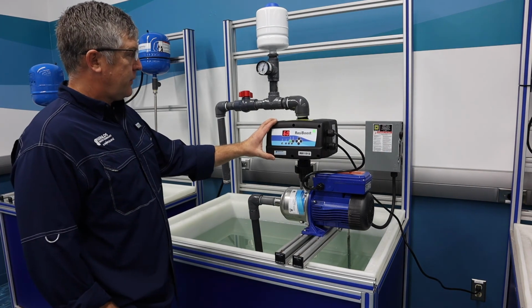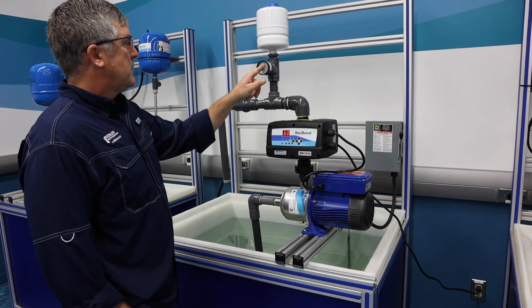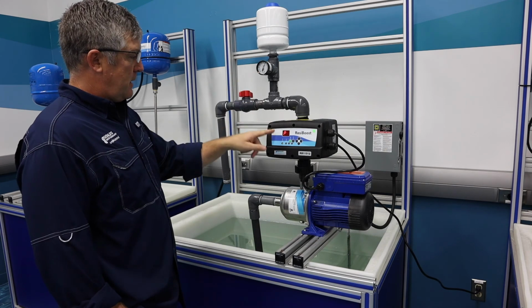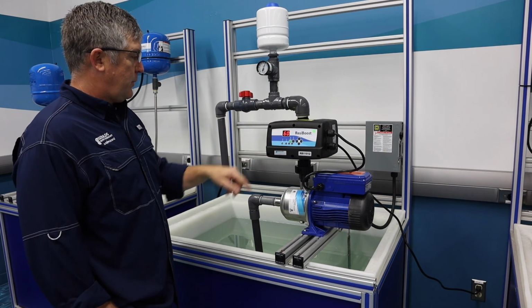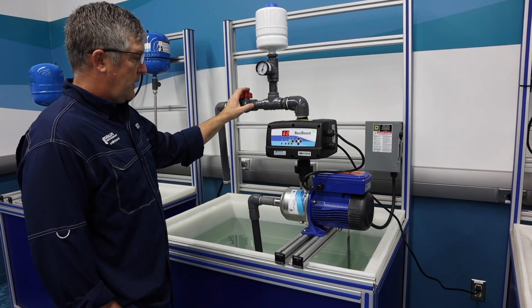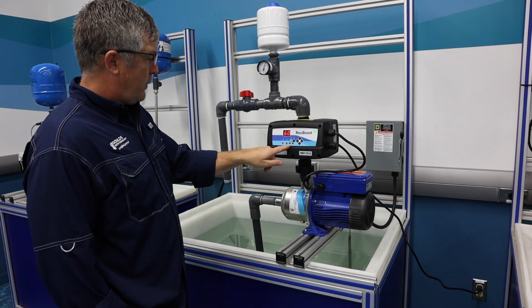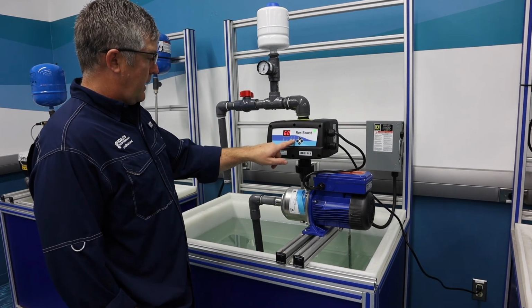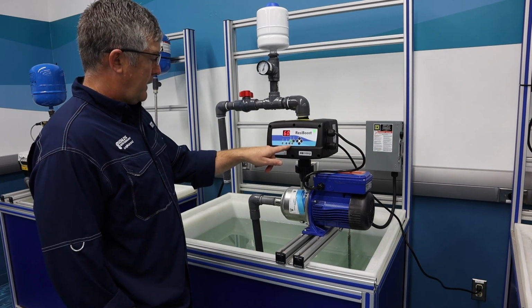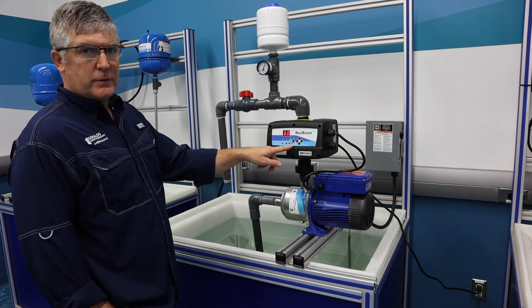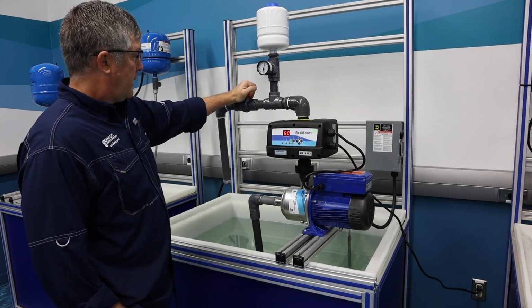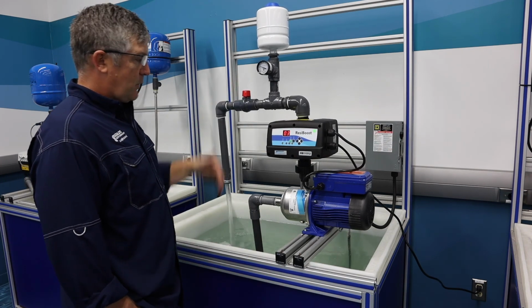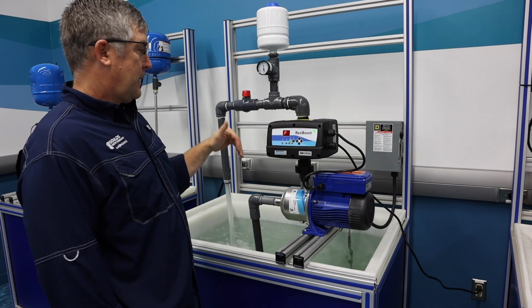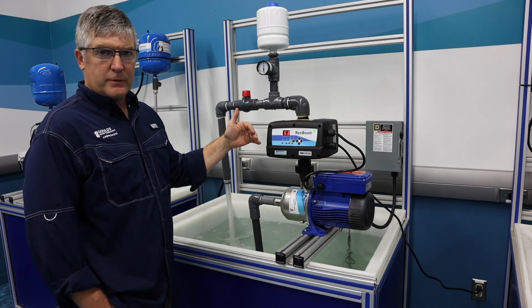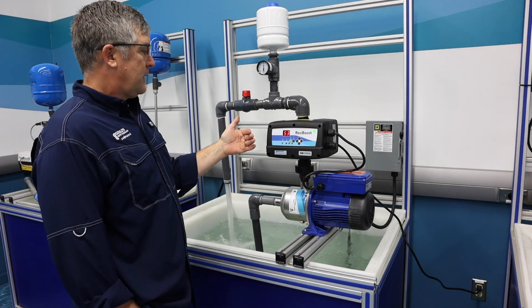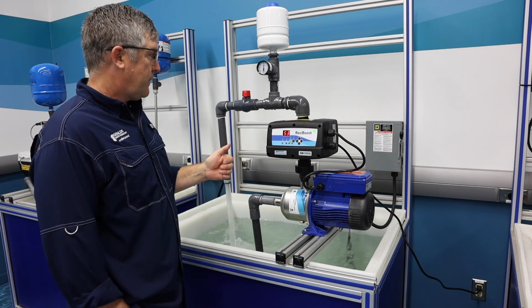Okay, so we can see our system here. Our pressure gauge is 60, and I'm showing 60 on the ResiBoost. I've got my valve closed. But notice here that I'm still in the manual mode. So I want to get that into the automatic mode, which is looking at the transducer. Let's just crack the valve. So we get that pressure drop, which in our case was 54 psi, and that turns it back on.